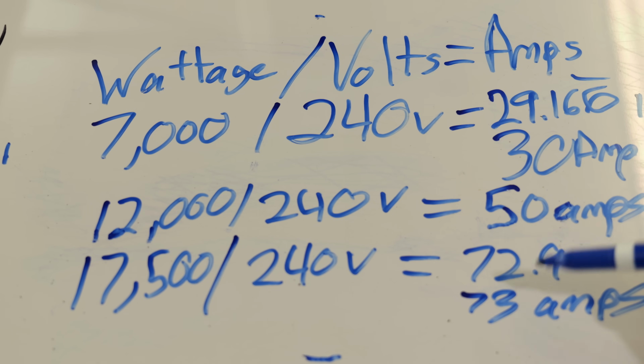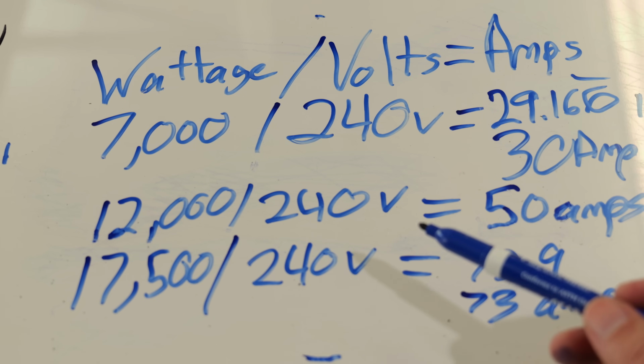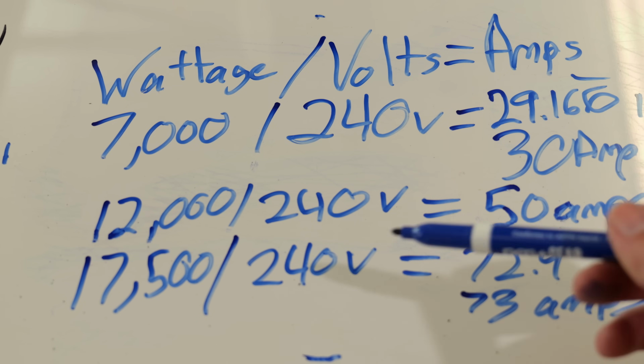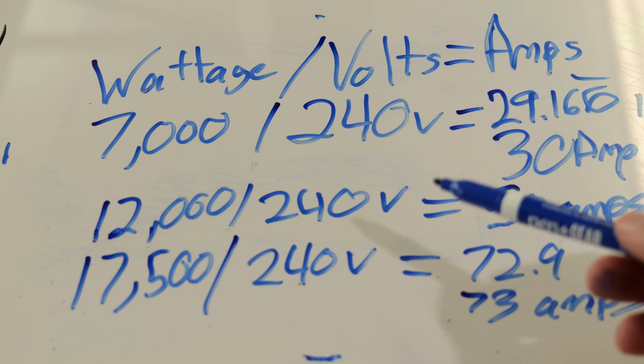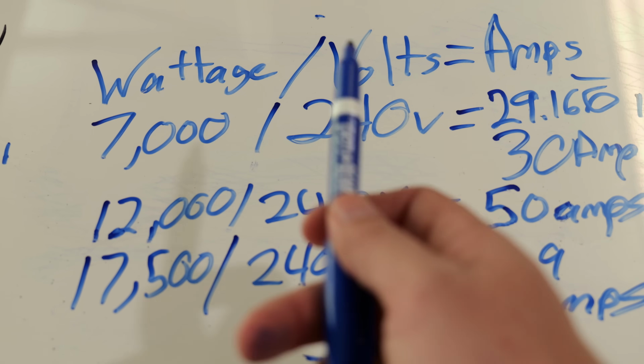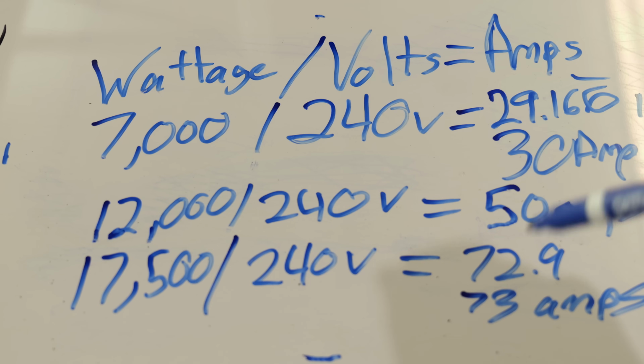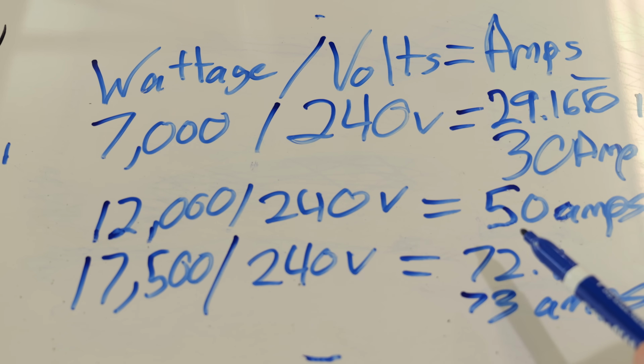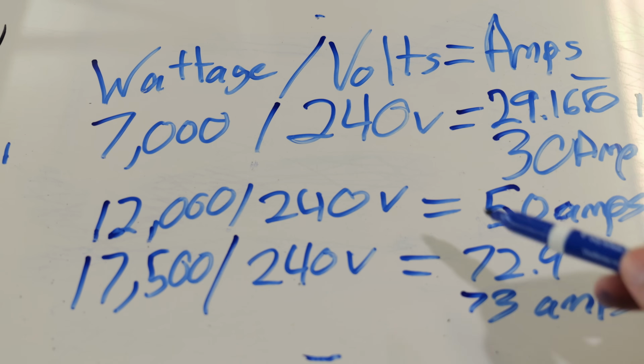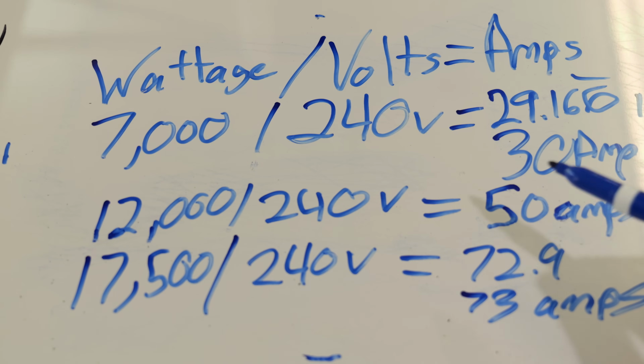So which power inlet box do they get if their generator is capable of supplying 73 amps? Well, the thing is, most of your portable generators are not necessarily made to be connected to houses. They're most oftentimes designed for contractors on construction sites, so they can have multiple things plugged into that generator all at once. They can have a 50 amp and a 30 amp cord all plugged in, and it's capable of supplying that 73 amps. So in that case, while your generator might be capable of the 73 amps, you're still only going to get 50 amps of production, because that's the largest outlet that is on that generator. Because if you try to go above that 50 amps, then the circuit breaker on the generator is going to trip, and you're never going to get anywhere near the 73 amps anyways.